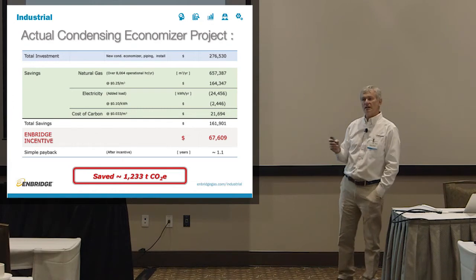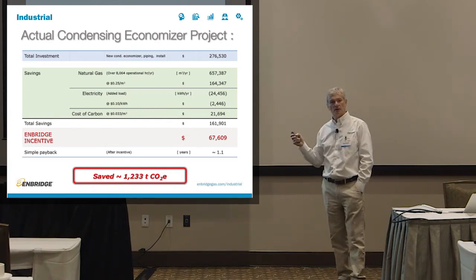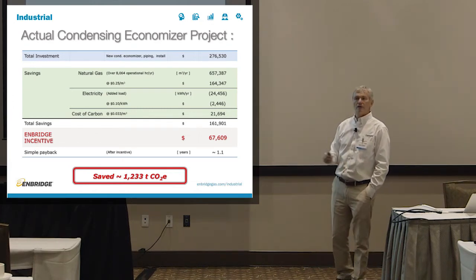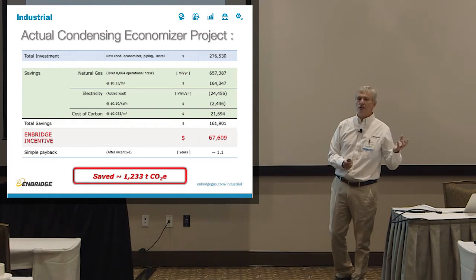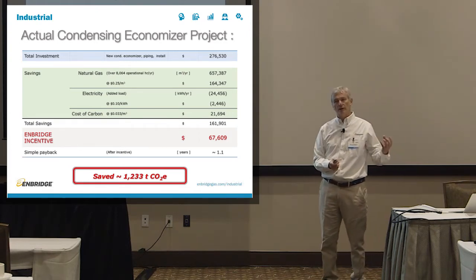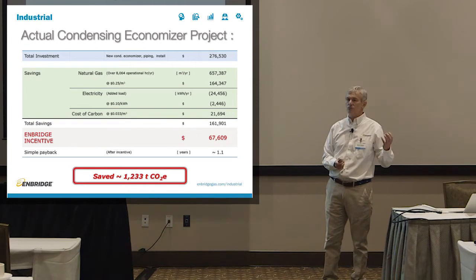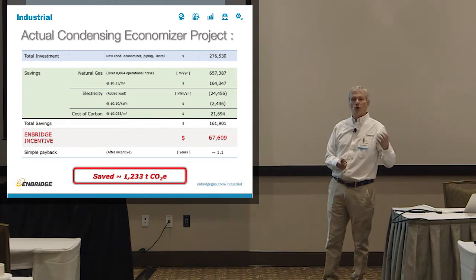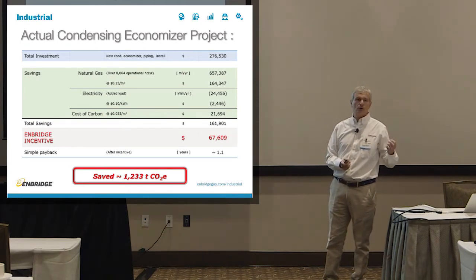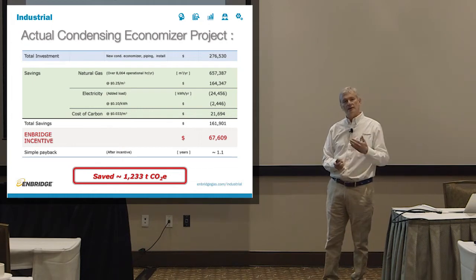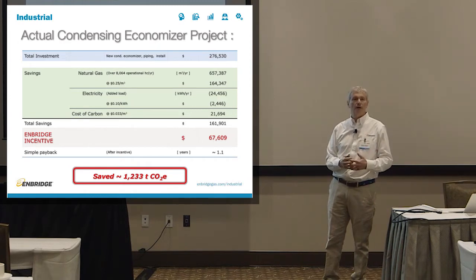And the funny part is they actually had a steam boiler for steam, and then they had a direct contact water heater for the water heating that was natural gas as well. We completely eliminated the need for the direct contact water heater. We just use waste heat to preheat all of their water. And it's about 15,000 pounds of water every hour.